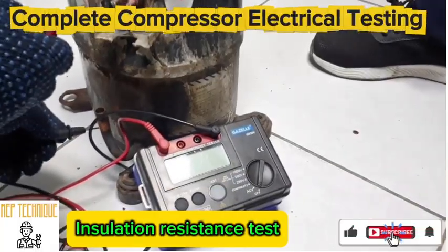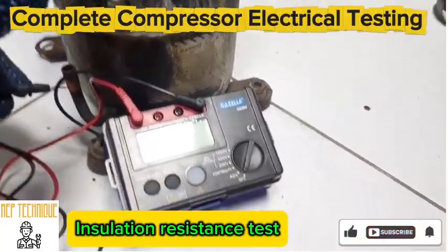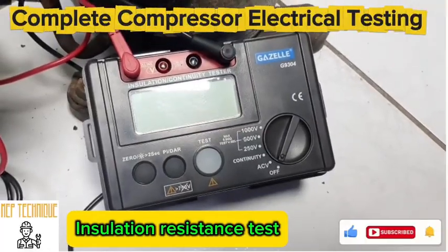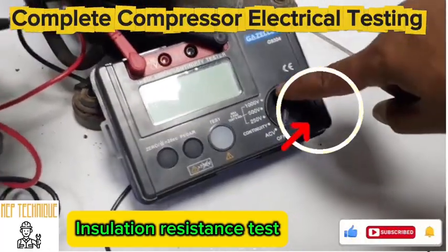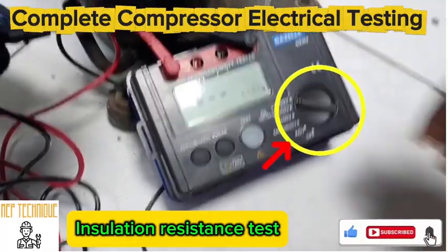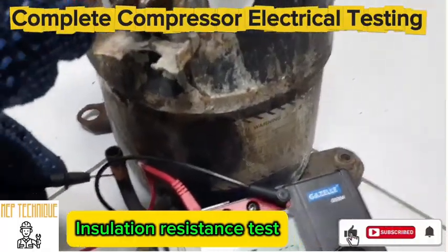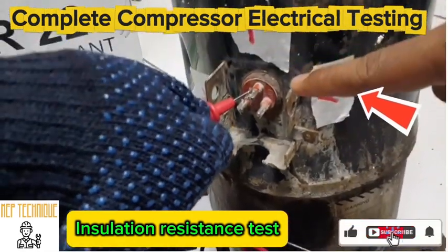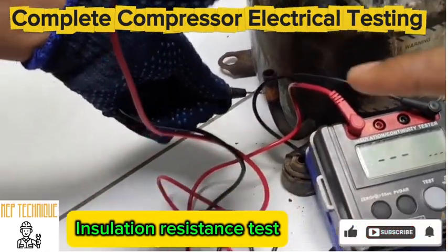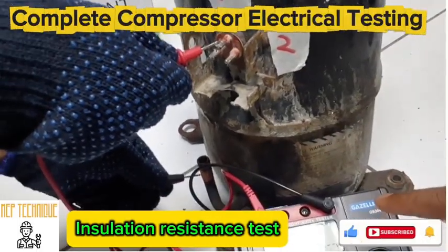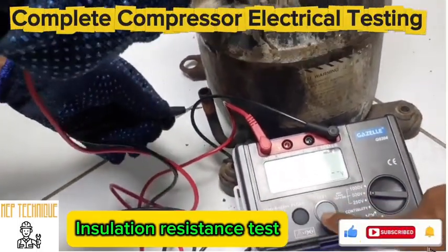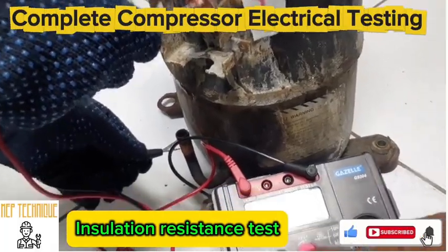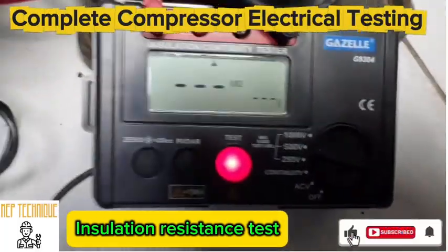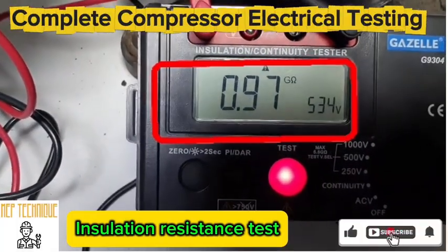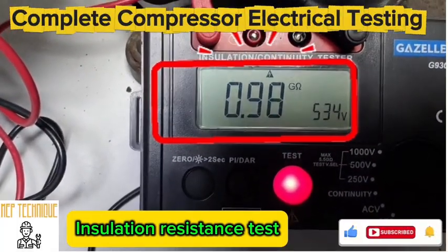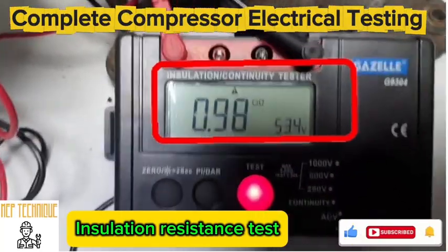So now we are going to check the insulation of the compressor. We took a high insulation tester, or Megger. We will provide 500 volts DC to the compressor. There are 2 terminals: the line will be connected to the compressor terminal and the ground will be connected to the body of the compressor. Once we apply 500 volts DC, press the test button to check the insulation resistance reading. When you press the test button, the insulation shows 0.97 giga ohm.